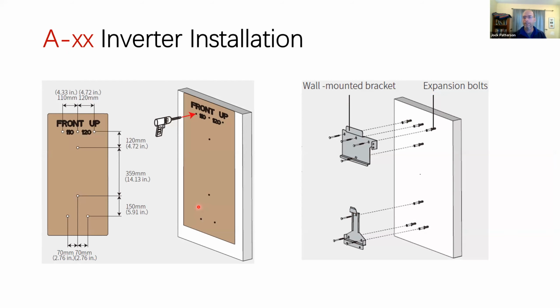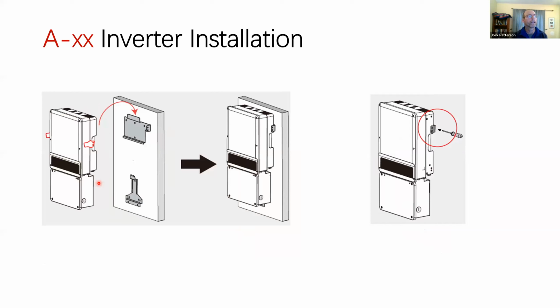Installation here is being shown not to really give you a step-by-step of how to install, but rather to show you that this should be pretty familiar, right? You're putting up with fasteners a mounting bracket and you're hanging the inverter. The inverter comes with a template. It's the first thing you pull out of the box. So you don't want to throw that away. That's your template, right? Makes it much easier to line up the brackets. And then you hang the inverter, and you can even put a lock in it for anti-theft. The inverter is going to normally be standing up, but it could be reclined back, I think 15, maybe 20 degrees, so it doesn't have to be perfectly vertical.